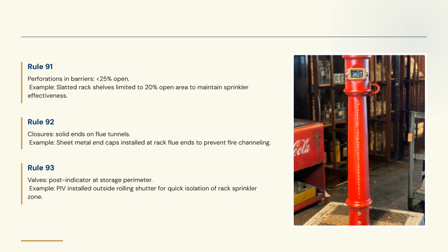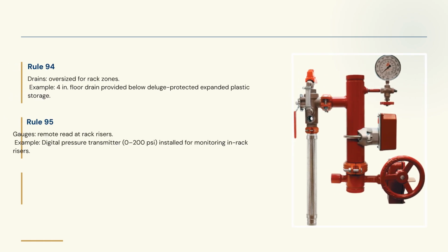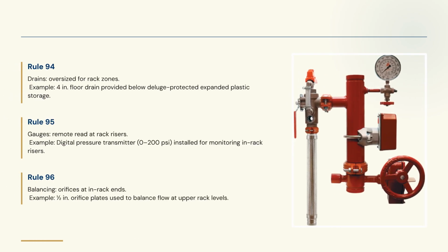Rule 93 mandates post-indicator valves at the storage perimeter for quick isolation. Rule 94 requires oversized drains for rack zones. Rule 95 mandates remote read gauges at rack risers. Rule 96 specifies using orifices at in-rack ends for flow balancing.